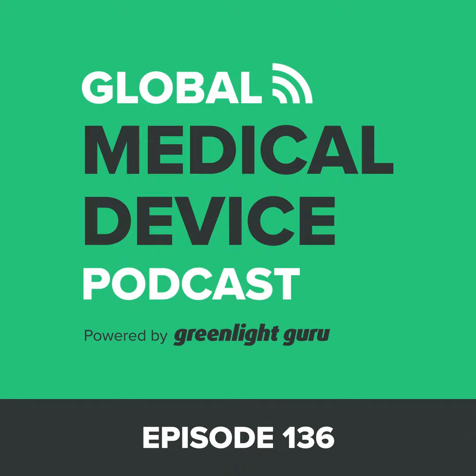Let me answer the other part of your question, John, which was the types of devices and the types of 510Ks that are eligible for eSTAR, at least right now. So FDA specifically includes the 3 major types of 510Ks: the traditional, the special, and the abbreviated, as long as you're planning on submitting one within the next 3 months.